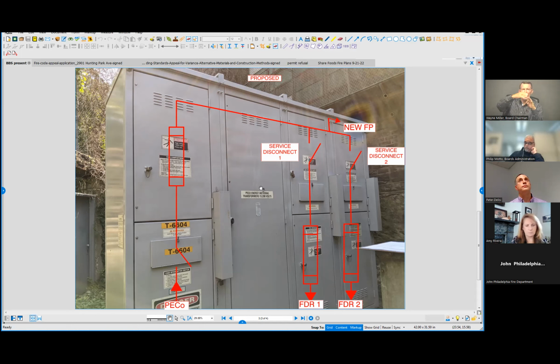What would be needed to take care of that? What would they have to do? Probably spend another $60,000. So what would be needed would be a tap into the medium voltage line. We would have to have a disconnect switch. We would have to have a new CT and PT cabinet because it needs to be metered by PECo. And all that gear would need to be located outside of the building. Working at medium voltage takes a specialized electrician. It's not inexpensive. I think we're easily in the six figures on that modification.